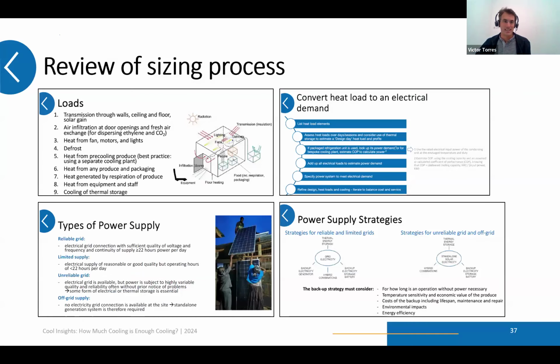Let's go to the next slide to review the design process again. The first step, as Jeremy mentioned, is to analyze the heat load of the cold room, based on different aspects shown here in 9 steps, well described with equations in section 4 of the guide. Most important is analyzing thermal losses through the walls, air infiltration, and the amount of products introduced into the cold room, plus whether you have pre-cooling and separate rooms for storage versus pre-cooling.